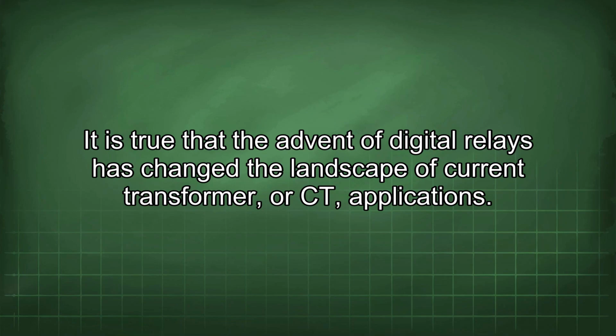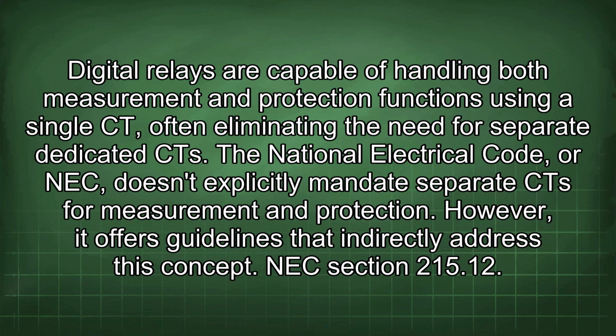It is true that the advent of digital relays has changed the landscape of current transformer, or CT, applications. Digital relays are capable of handling both measurement and protection functions using a single CT, often eliminating the need for separate dedicated CT. The National Electrical Code, or NEC, doesn't explicitly mandate separate CT for measurement and protection. However, it offers guidelines that indirectly address this concept.